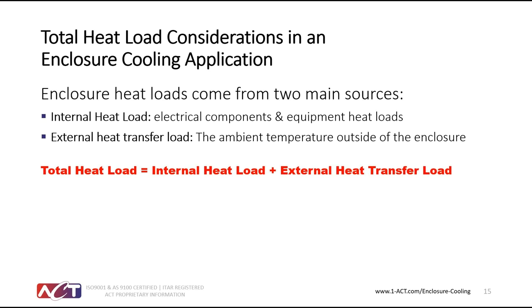And then total heat load considerations come from a couple of things. Two main sources are the internal heat loads of the electrical components and equipment, and then, of course, the external heat transfer loads from the ambient temperature outside of the enclosure. So something like a sun load, or if your panel is located near a furnace, some of that heat can be brought back into your system. So you have to take a look at both of those things in your calculation to figure out what size heat exchanger or what size air conditioner you would need in an enclosure to cover those loads.